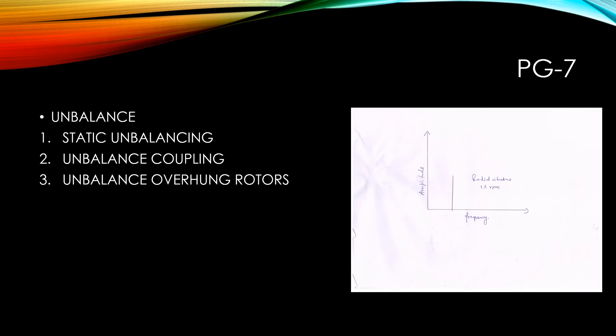For all types of unbalance, the spectrum analysis will show a predominant 1x RPM frequency of vibration. The vibration amplitude at the 1x RPM frequency will vary proportional to the square of the rotational speed. It is always present and normally dominates the vibration spectrum.